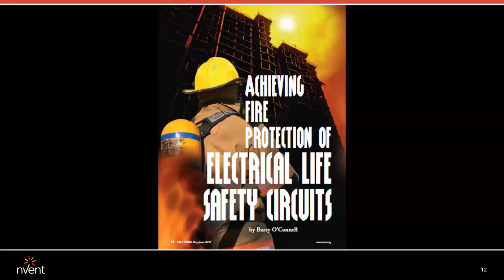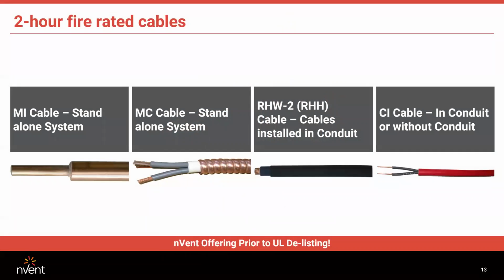And there are various ways of achieving fire protection of these life safety circuits. There's the MI cable. You have MC cable on the market. You have your RHW cable. And then, of course, you have a circuit integrity type cable. Now, all of these cables, with the exception of MI, have run into listing problems with UL and have other issues, which I will get into later on in the presentation.